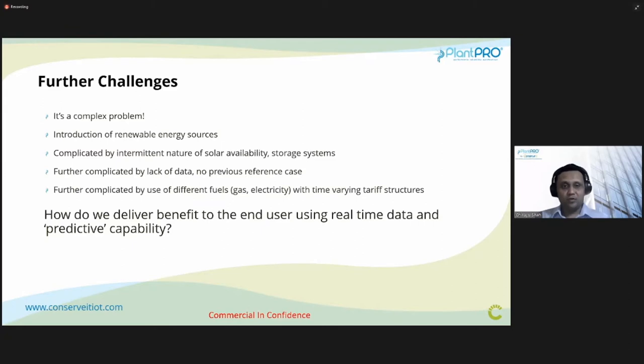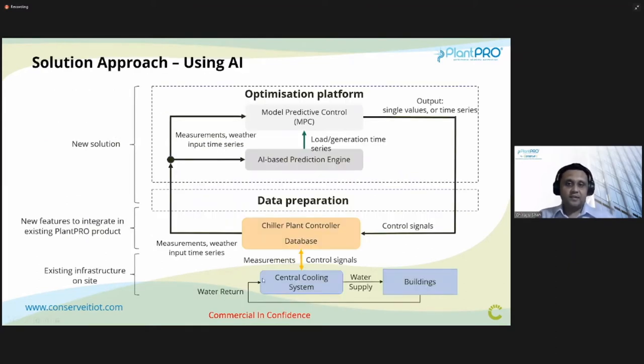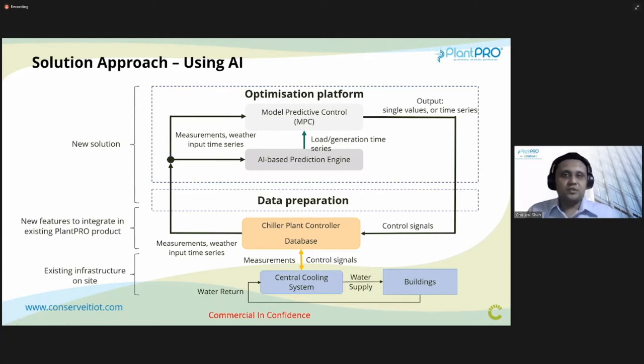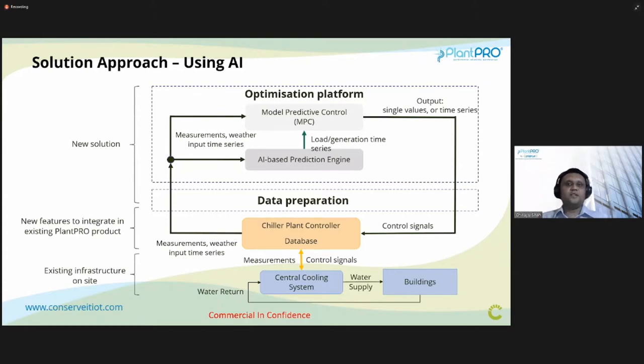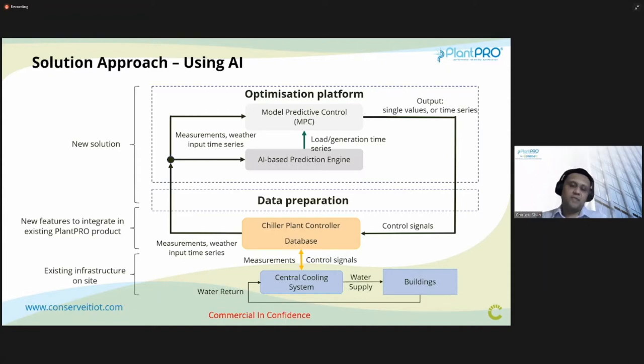The key question is: how are we going to deliver benefit to the end user using real-time data and predictive modeling capabilities? The solution approach uses AI. At the bottom is your central chiller plant supplying chilled water to buildings. On top of that, we propose a smart machine learning chiller plant solution — a product called PlantPRO. Above that is an optimization platform: model predictive control and an AI-based prediction engine, with inputs including measurements and weather series, and outputs including MPC calculations that send controls back to the central plant controller.